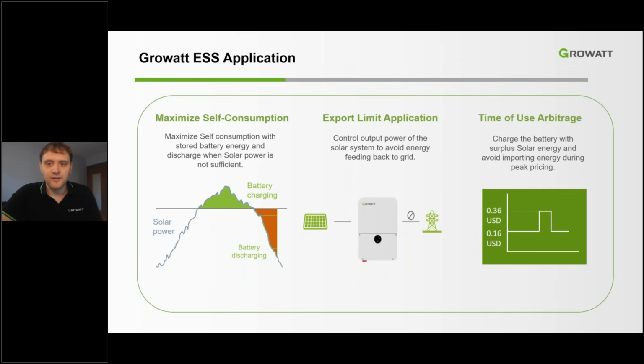So to put all of this together, the hybrid functionality of the MIN device is proven to maximize your customers' reliance on stored renewable energies. Charging the battery with solar energy during the day and discharging to the customer loads during the night. The MIN inverter has zero export configuration possibilities to avoid limitations imposed by utilities to control the exportation of energy to the grid. When zero export features are being used in certain circumstances, the battery is charged with clipped solar energy that would normally have been exported to the grid.